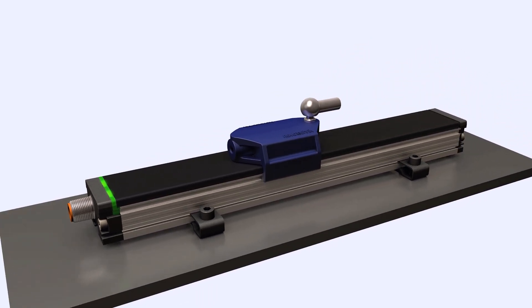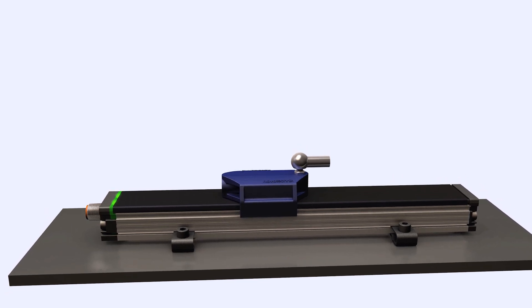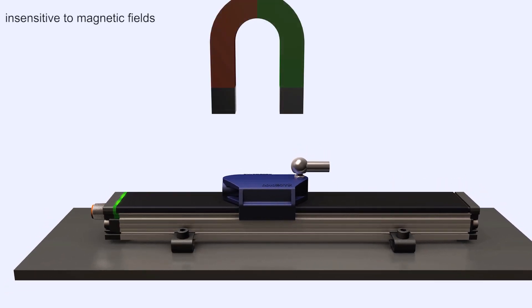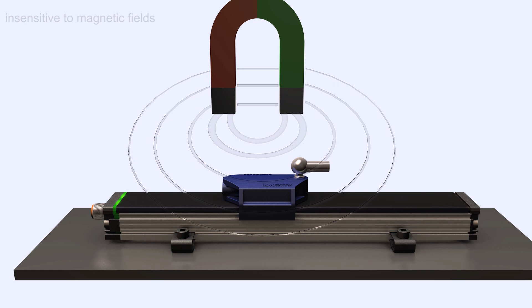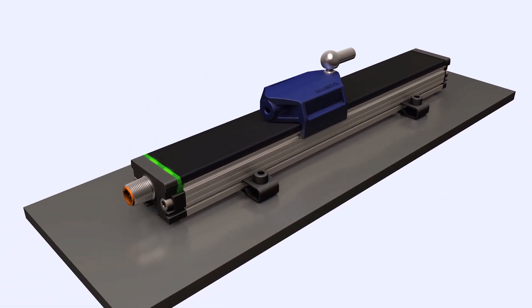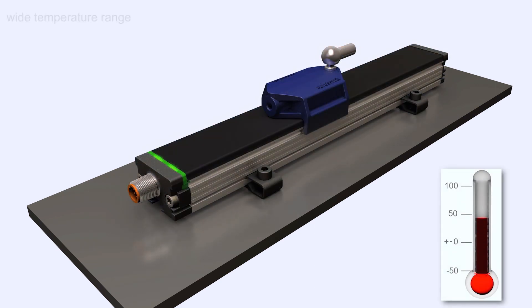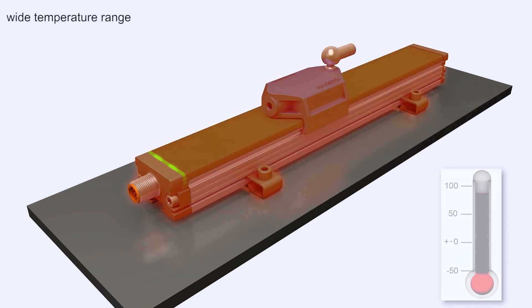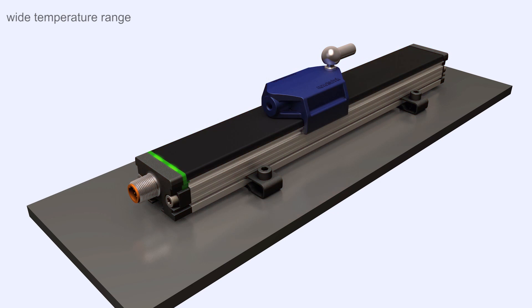NovoPad technology is insensitive to magnetic fields produced by powered devices like electric motors, hydraulic valve switches, or variable frequency drives as the position is not detected by a magnetic field but by an inductive field. The TF1 series of sensors operates over a minus 40 to plus 85 degrees Celsius temperature range.